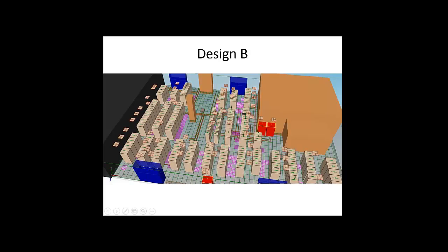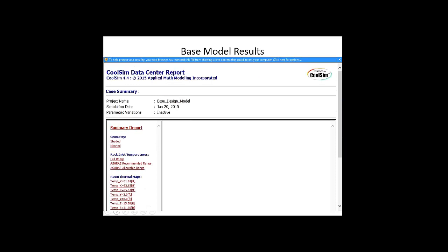If you look closely, you'll see the airflow direction on these is out and right into the cold aisle input of these. So this is what we call classroom. The inlets are all facing the same direction. But this is a hot aisle right here. These are actually facing each other, so that they did make a hot aisle there. Very typical kind of situation that I often encounter. So we'll take a look at this one.